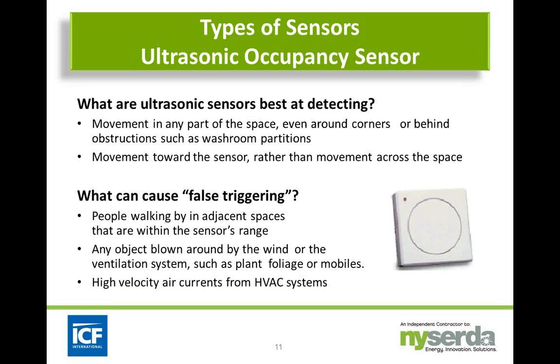They're good at detecting movement pretty much in any part of the space. They can see around corners. They can see through obstructions. One of the places that we see ultrasonic used quite often, or maybe dual technology, is in washrooms, restrooms that have multiple stalls. That way you only have to have maybe one sensor in the space and it can cover the entire space despite the fact that there's a stall blocking the occupant from the sensor. So movement toward the sensor rather than across actually works really well with ultrasonic.